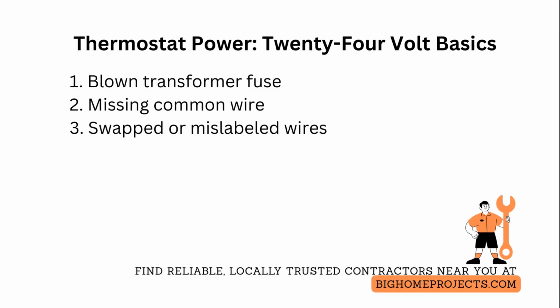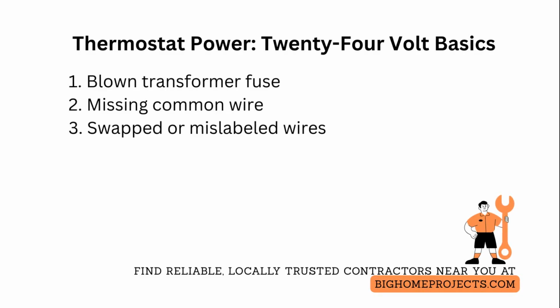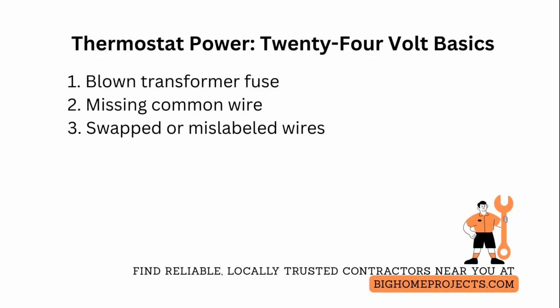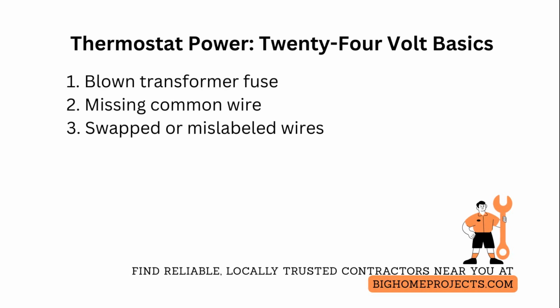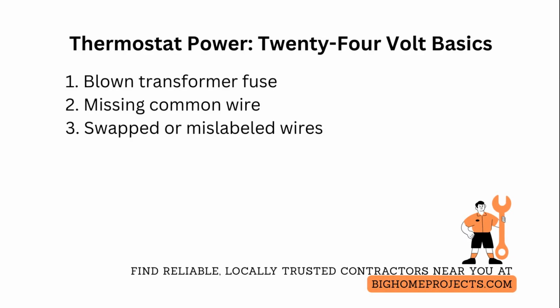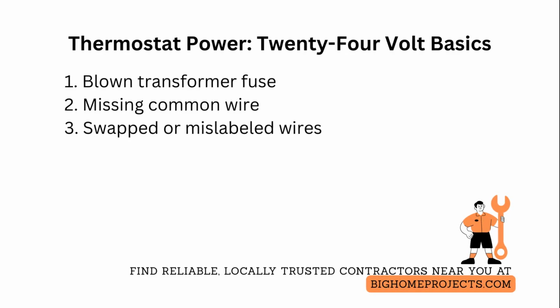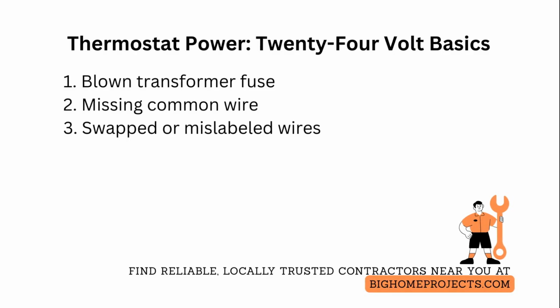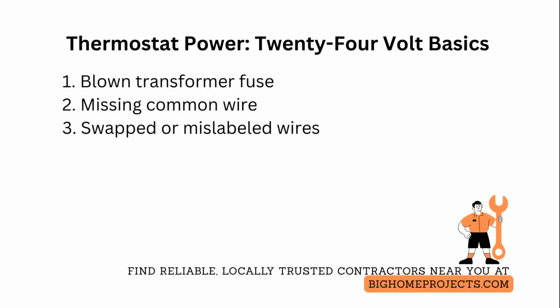One of the biggest issues is thermostat no power, or a dead thermostat from a blown transformer fuse, which shows as 0 volts between R and C. Fix it by inspecting and replacing the furnace board fuse with the exact amp rating and testing the transformer output before assuming wiring failure. One of the common problems is a missing common wire for new smart thermostats, leading to frequent reboots and brownouts. To resolve this, run a dedicated common conductor from the furnace C terminal or install a compatible common wire adapter kit and confirm a stable 24-volt supply.